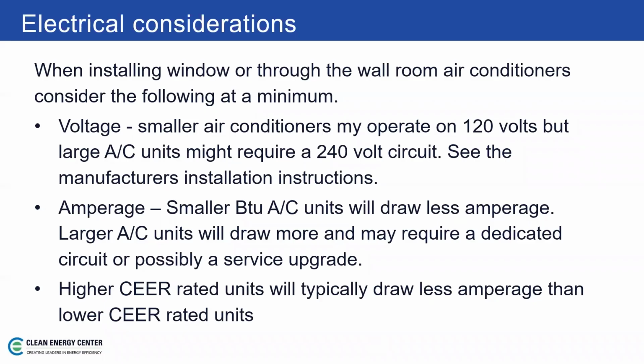The smaller BTU AC units tend to draw less amperage, obviously. Your larger ones are going to draw more, and you're going to get to a point where you really need to consider that. If you're going to plug into an existing receptacle, you need to understand what else is on that circuit, how it's being used, and how it's fused. Is it really going to service the need of this window air conditioner? I know we get into some older homes, so you're going to have to look at that fairly closely to make sure you don't make a mistake and start blowing fuses. Understand, if there's never been air conditioning installed before, there's a good chance you may have to do some electrical work to put these in. Higher SEER rated units typically draw a little less amperage than lower SEER rated units. That goes along with the gain in efficiency.